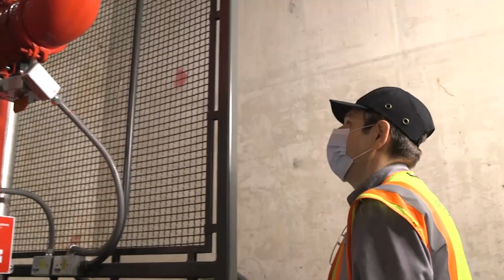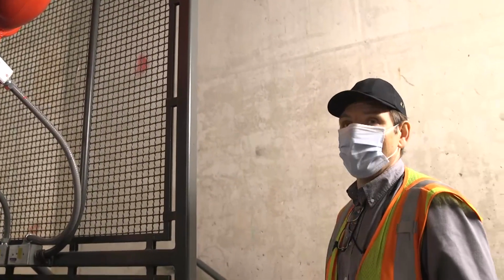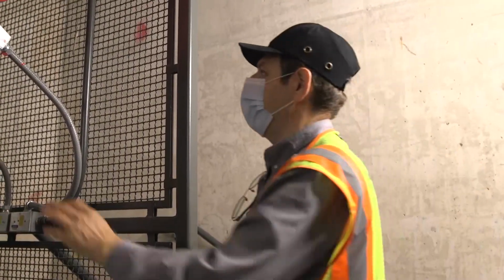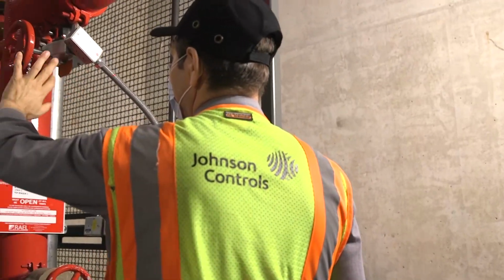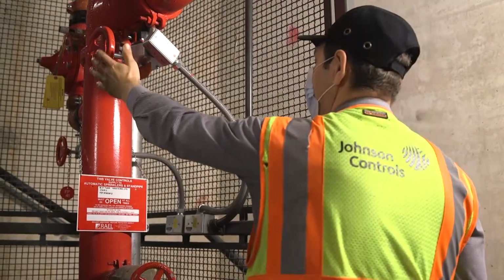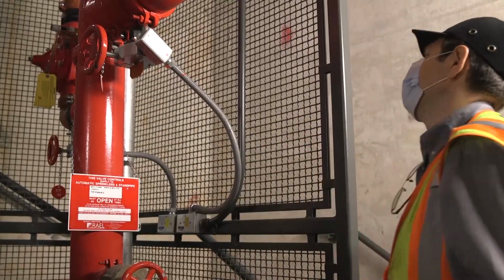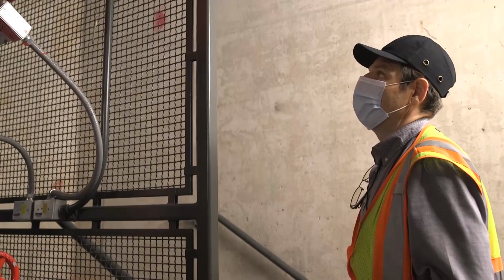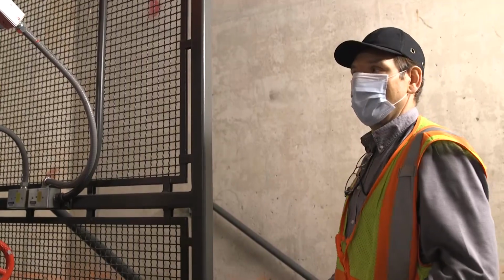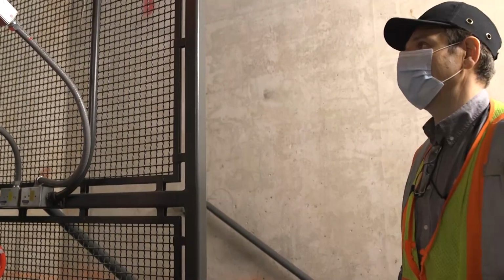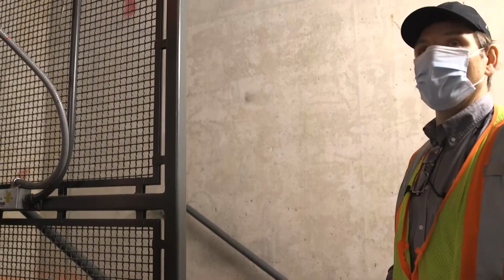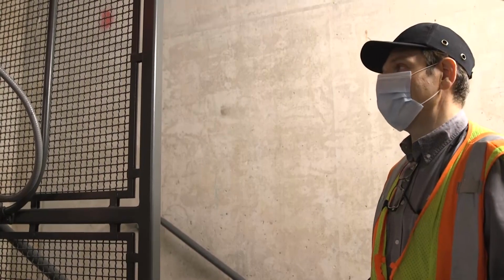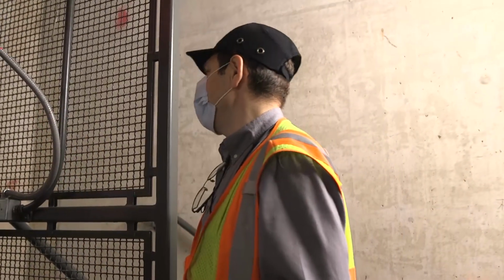So this is an automatic device. Any water flow activated, it's automatic activation. Tamper switch, that's a manual. So somebody has to manually turn the valve to activate it, right? But water flow is automatic, so it gives you an alarm automatically, like a smoke detector or also duct detectors. That's part of the automatic devices. Only the manual pull station will be a manual alarm, right? In this case, the supervisory of the tamper switch is a manual activation.